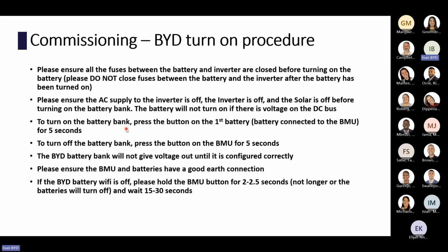To turn the BYD battery bank on, you just hold the button on the first battery and all other batteries will turn on. To turn the battery bank off, just hold the button on the BMU for 5 seconds. The BYD battery bank will not give out voltage until it is configured correctly. That's just something to keep in mind. If you're turning on your battery and nothing happens, it's probably because of that.